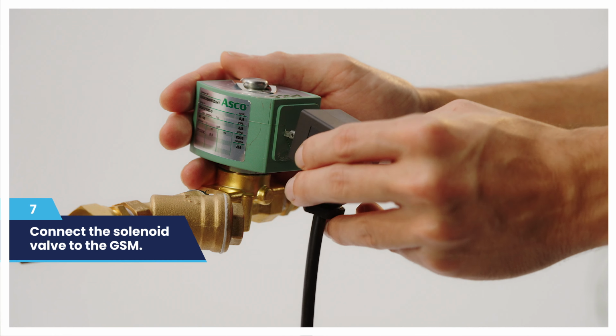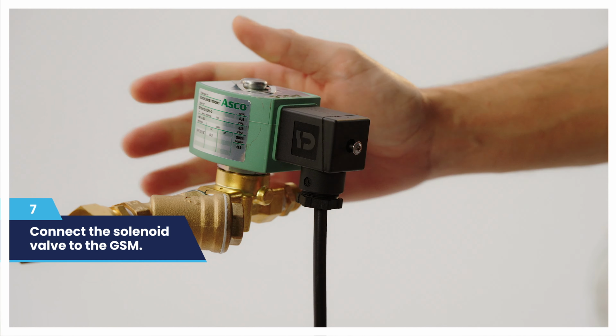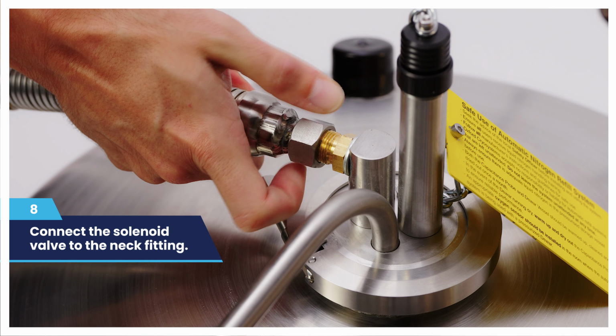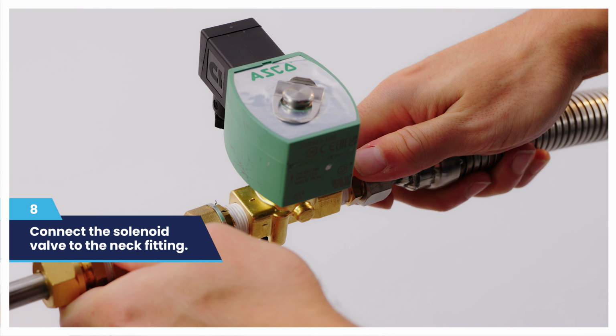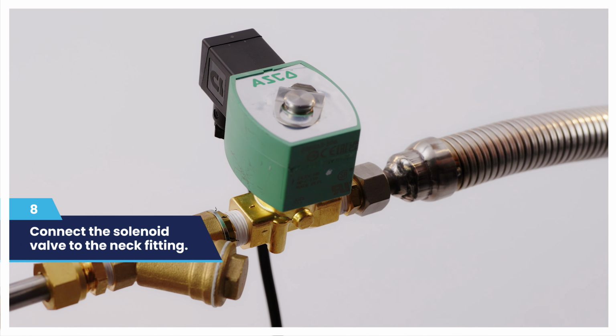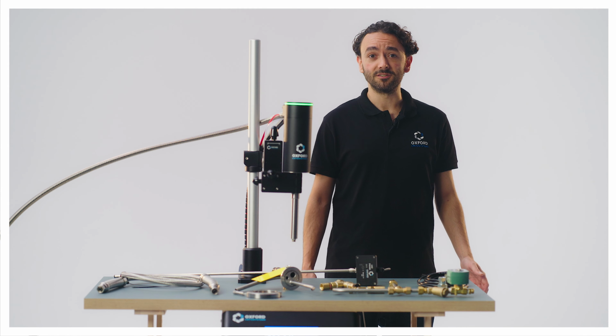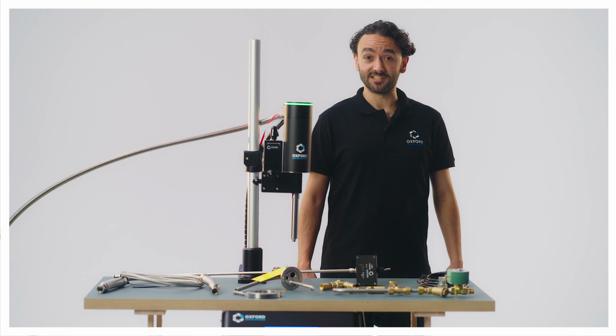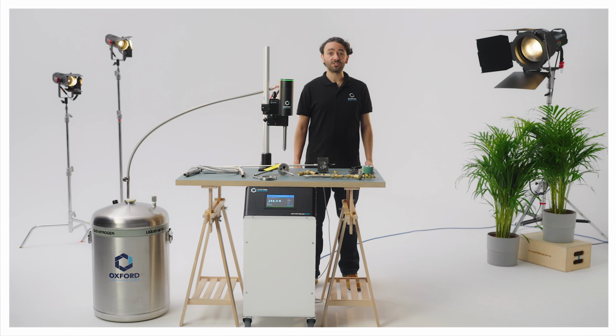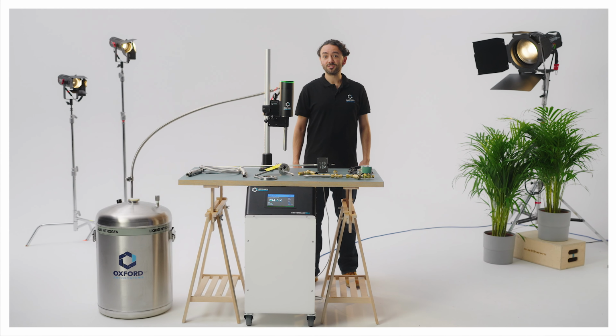Finally, connect the solenoid power cable to the Autofill solenoid port on the GSM and the transfer hose from your supply dewar to the neck fitting. If you need a transfer line longer than 1.5 meters, make sure you use an insulated one. For more information about the Autofill, please refer to the Cryostream Handbook.